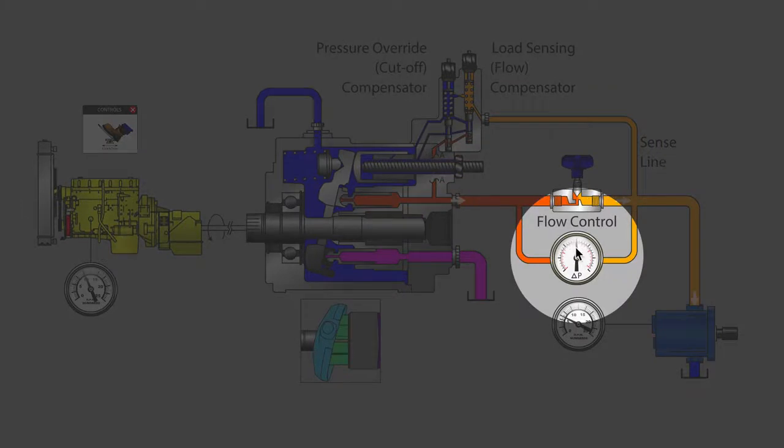If you're watching our special pressure gauge that has two inlet lines, called a delta P gauge, a differential pressure gauge, what you'll notice is that there are some minor little bumps as the prime mover speed changes, but it very quickly returns to its nominal value after the pump controller is done responding, doing what it needs to do.